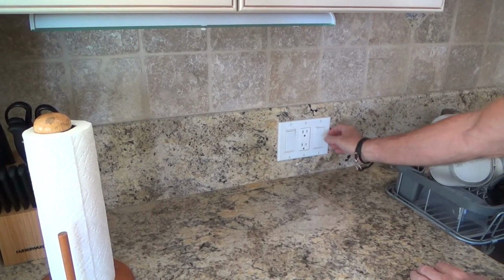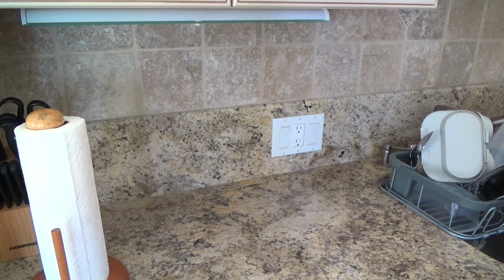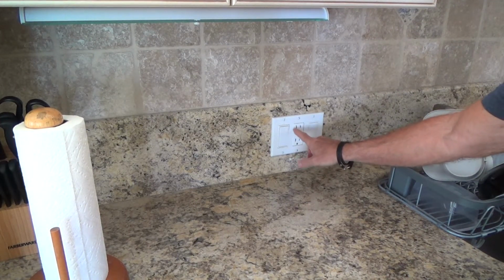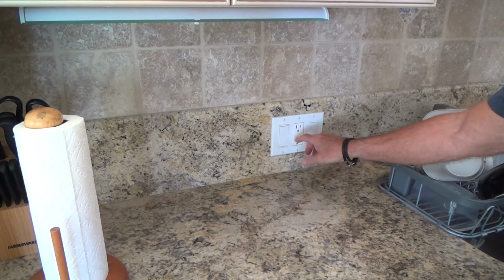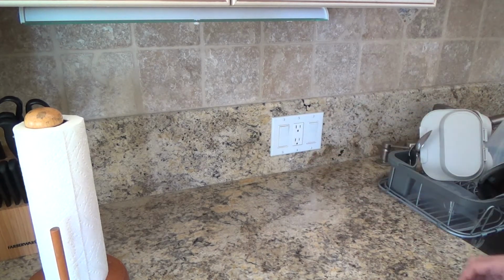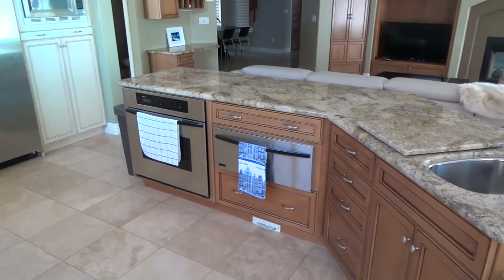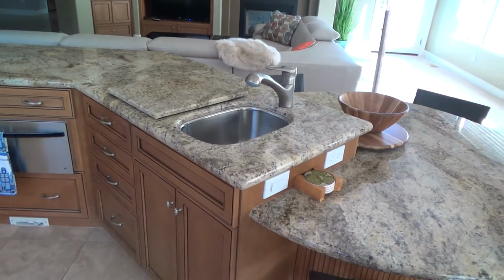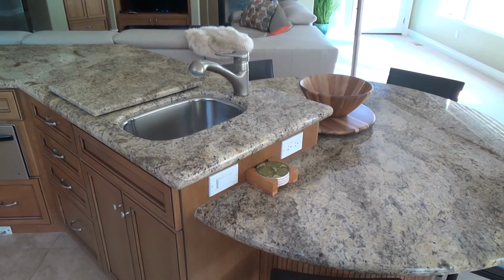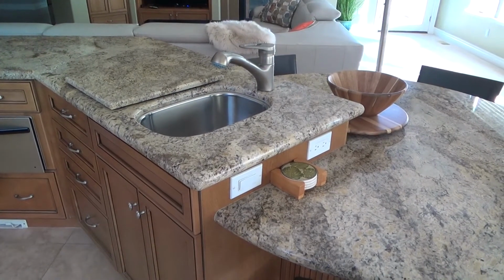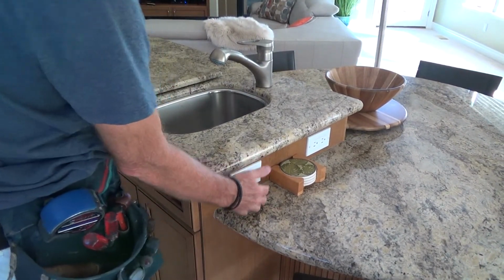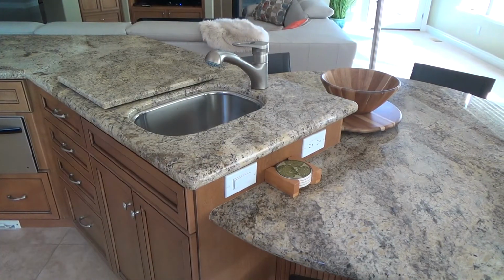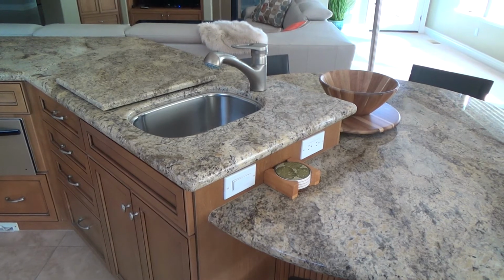Okay, so I found another breaker, and this house has two panels. One panel had the electrical for the GFI kitchen outlet, and also the garbage disposal. Interestingly, I also found one labeled island garbage disposal, which was for this island—that's what you call this separate cabinet countertop area. It said electrical, didn't say GFI, it said garbage disposal and island, and that's what this switch is for. Interestingly, that breaker was not a GFI breaker.